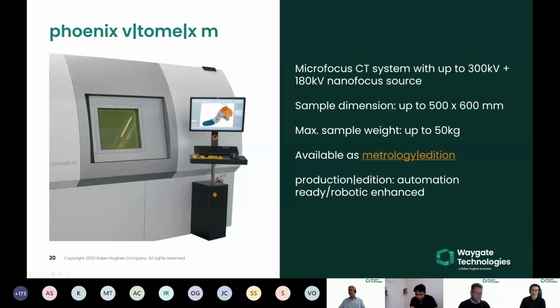You can see here some specifications of the system. If you're interested in that, there's much more, of course, on our webpage, or reach out to us and we can give you the full spec sheet of this system. Important for us here in this presentation is it is available as a metrology edition. So you can buy it as a standard CT scanner, and if you want, you can say, well, I also want it to be a metrology edition, so I want to use that for highly accurate and highly repeatable CT measurements. And if you do that, I want to show you what we do to make it a metrology edition.